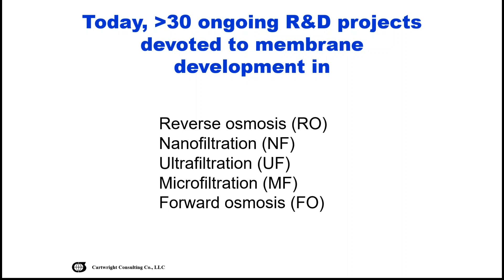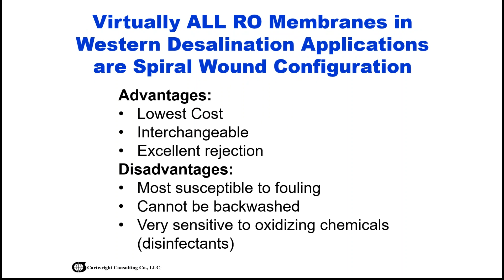He points out the developments in these different areas. Spiral wound RO membranes are still the most popular way to take out your ions in a reverse osmosis system. They have the lowest cost, they're interchangeable, and have excellent rejection. But they are the most susceptible to fouling, cannot be backwashed, and are very sensitive to oxidizing chemicals such as disinfectants.